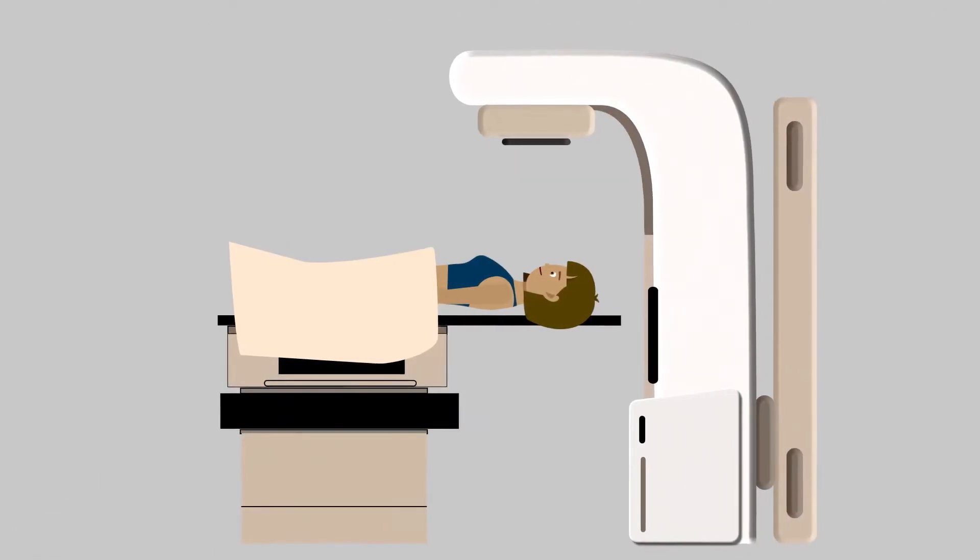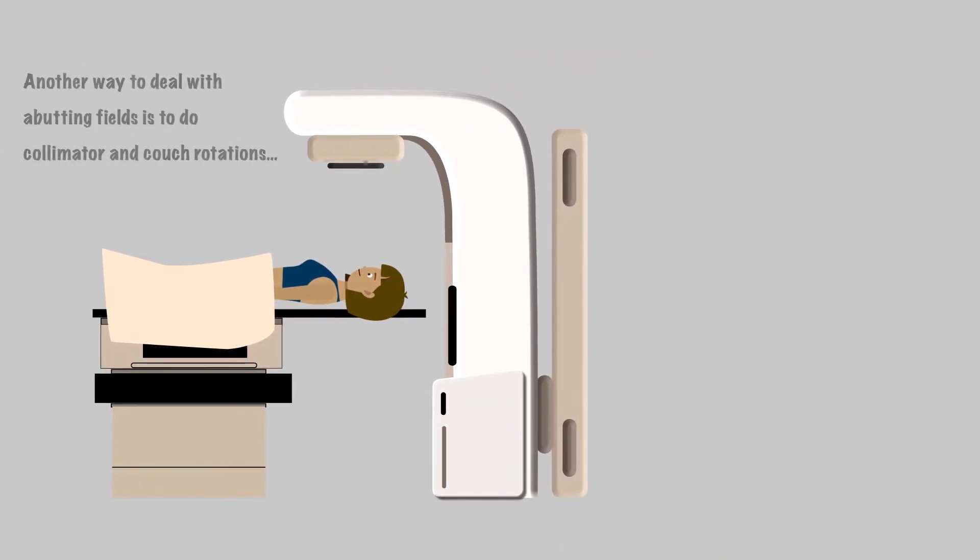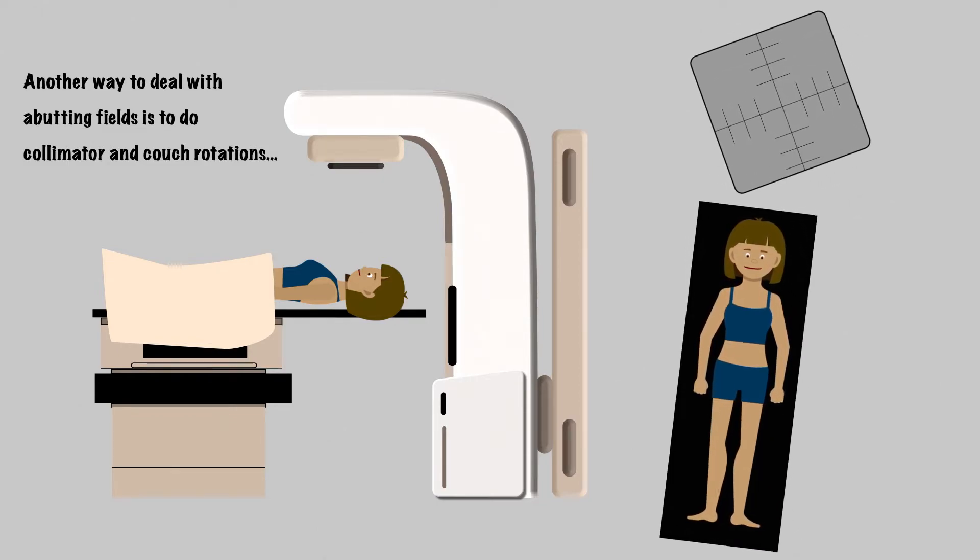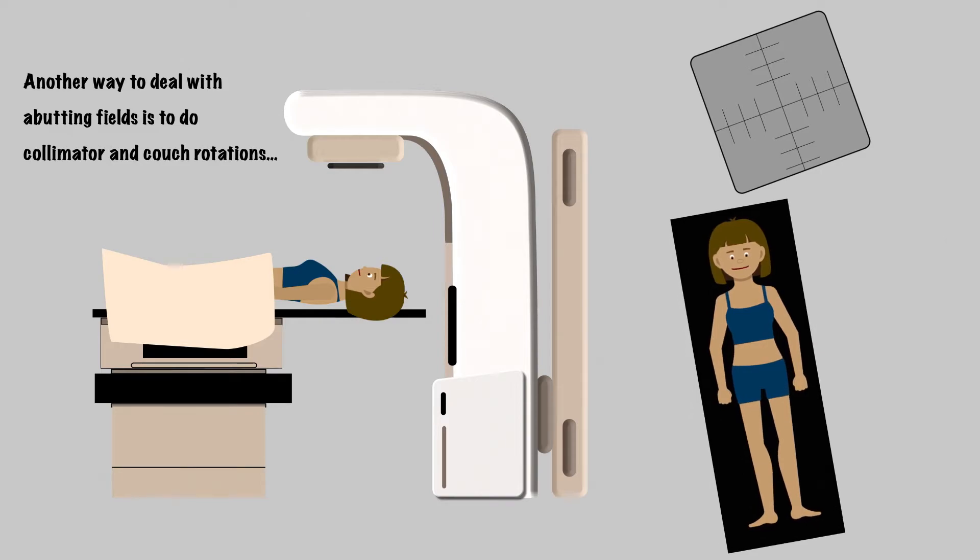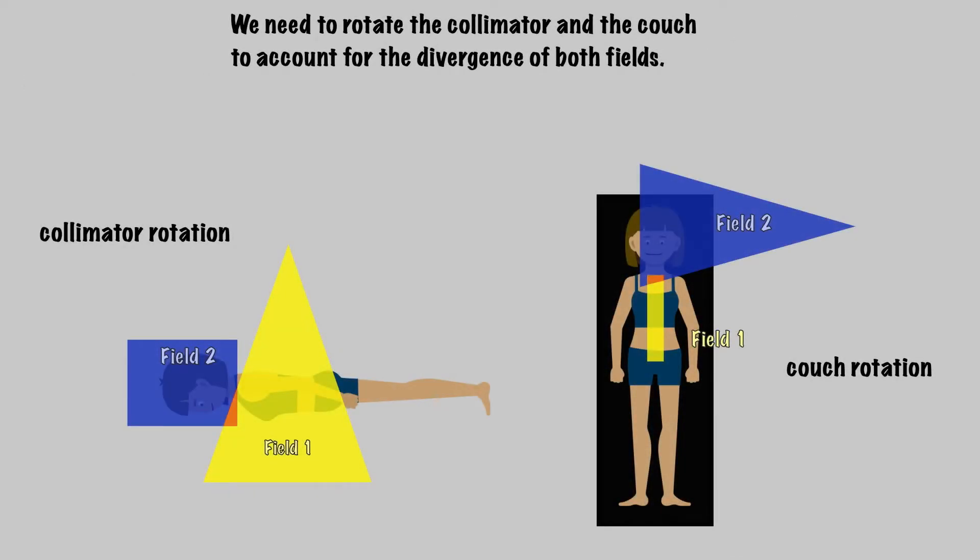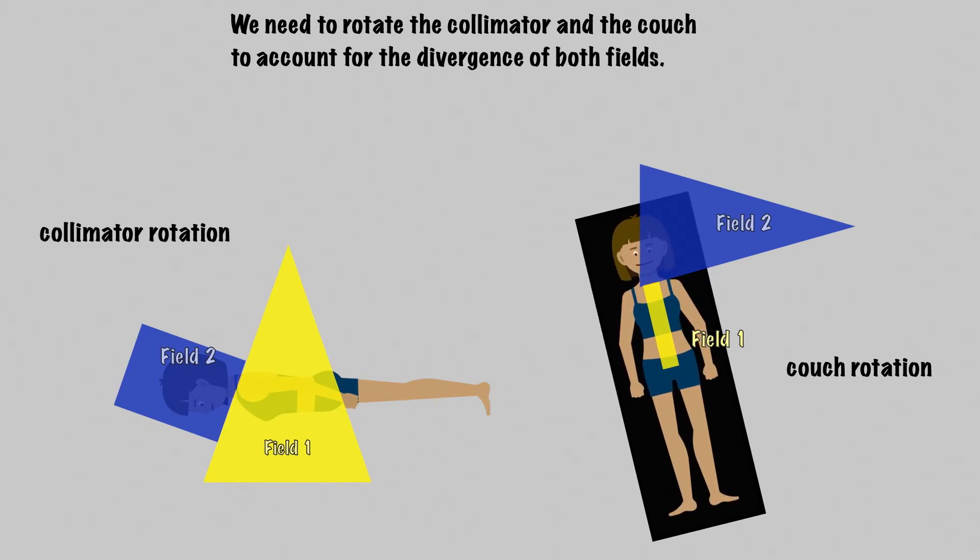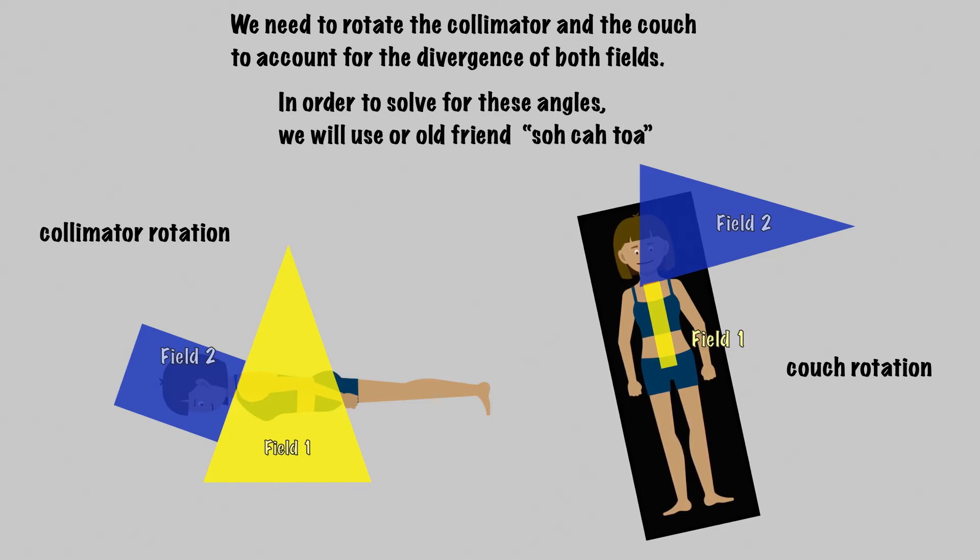The other way to match abutting photon fields is to use collimator and couch rotations. These rotations do not utilize a skin gap, but actually match the divergence of the beams so there aren't significant hot or cold spots, and can be used in many scenarios with a variety of beam arrangements. The goal here is to rotate the collimator of field 2 to match the angle of divergence from field 1, and to rotate the couch to match the angle of divergence from field 2. In order to solve for these angles, we will use our old friend SOHCAHTOA.